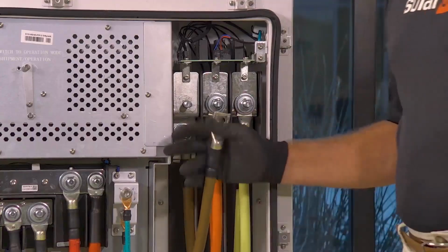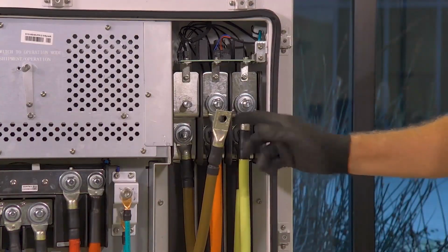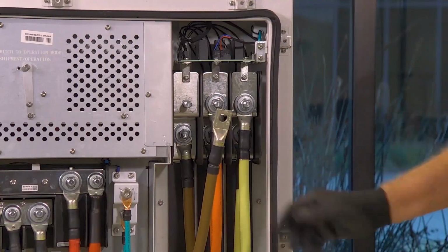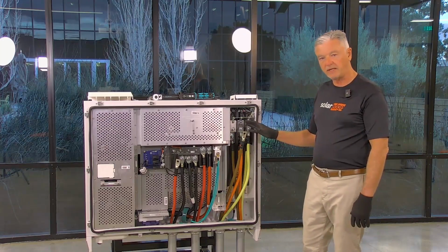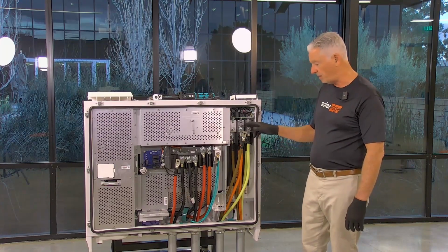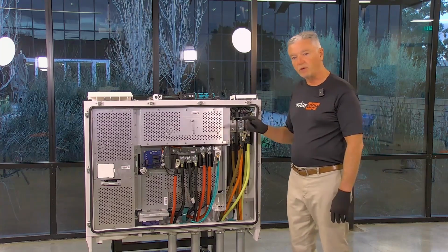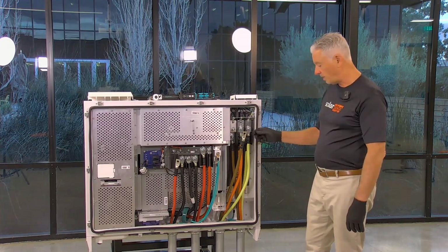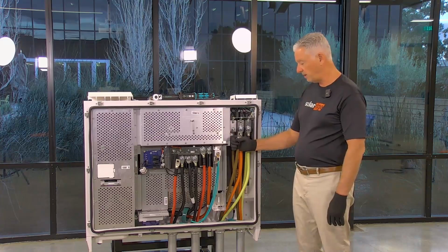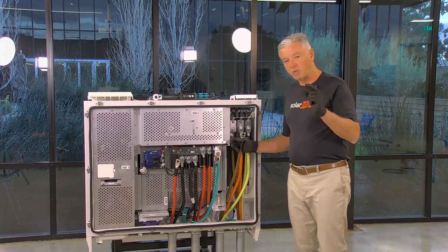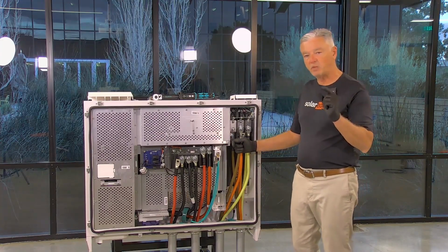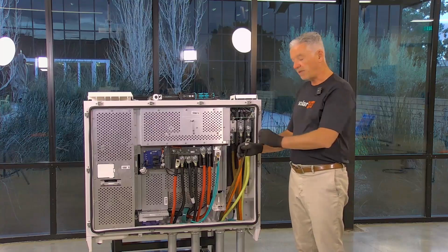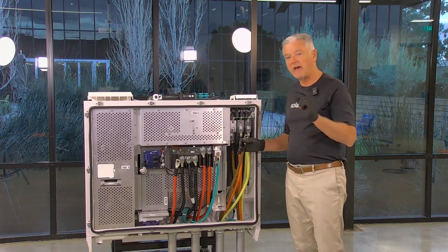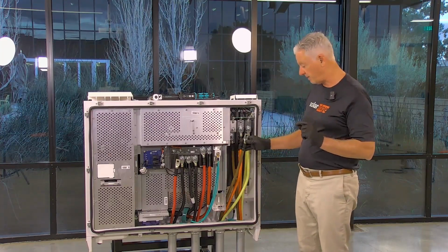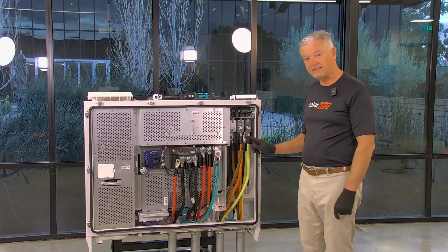It's a good time for us to talk a little bit about the compression lugs that are used and the conductor. So this terminal block can accept up to 600 kcmil conductor, each one, either copper or aluminum. The compression lugs have to be at the most 1.77 inches wide, and the thickness is at the most ½ an inch thick. The bolt hole size is ½ inch.